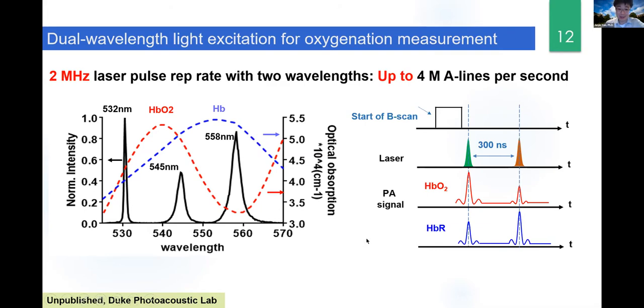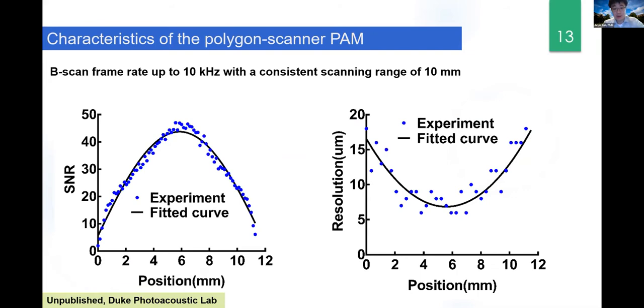Because the system is so fast, we have to sacrifice the depth range to accommodate that speed. We quantify the imaging performance: a scanning range of about 10 millimeters, achieving about 10 kilohertz 2D cross-sectional scanning. Sensitivity across the field of view and resolution are roughly consistent, which is very important — we do not want to sacrifice either sensitivity or resolution across this wide field of view.